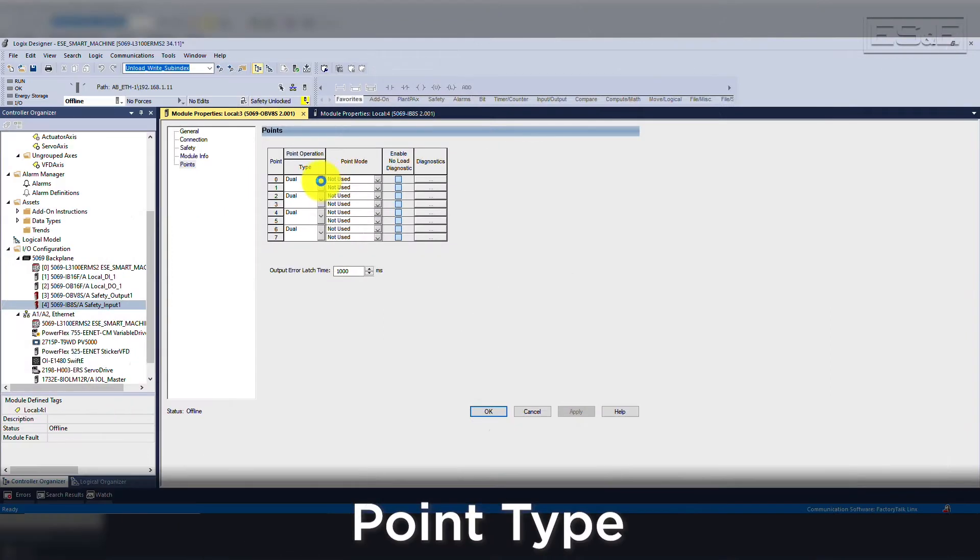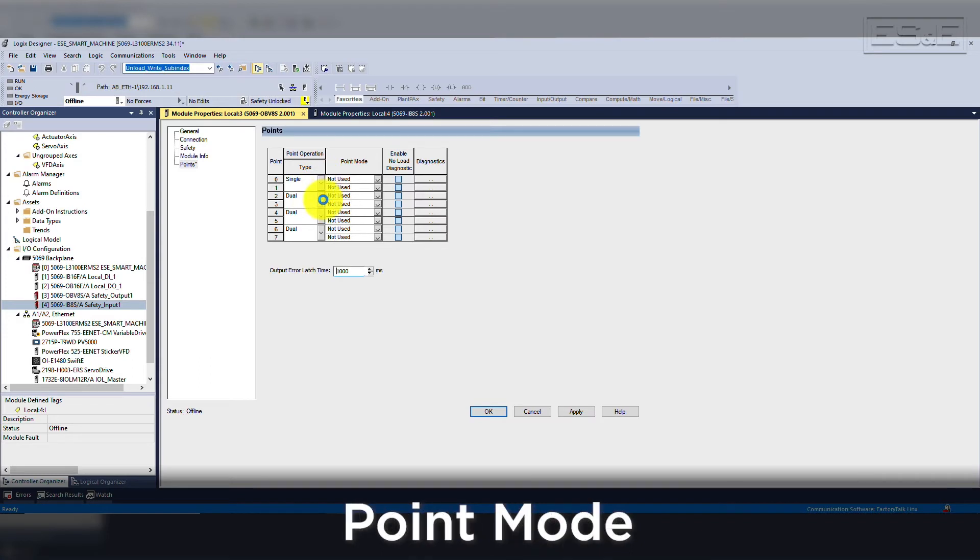For output cards, you have point type and point mode. Point type can be set up as single or dual. Dual was the traditional way for setup, but single allows more wiring options and has become more popular. Point mode can be set up for safety or safety with pulse test.